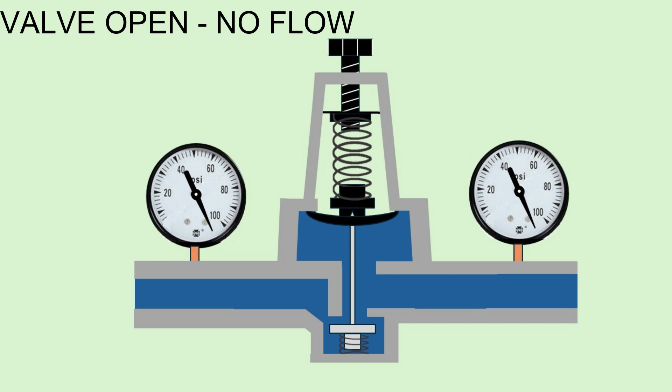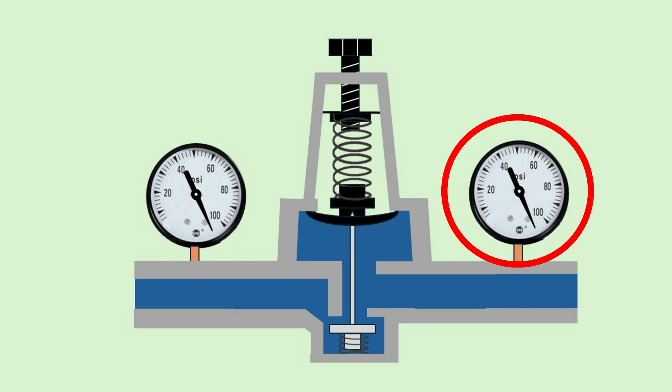This shows what would happen if there is no flow, but if the valve remained open. If this were the case in reality, then the water pressure in the home would be the same as on the inlet side of the PRV, because with no flow, there is no pressure drop across that gap.